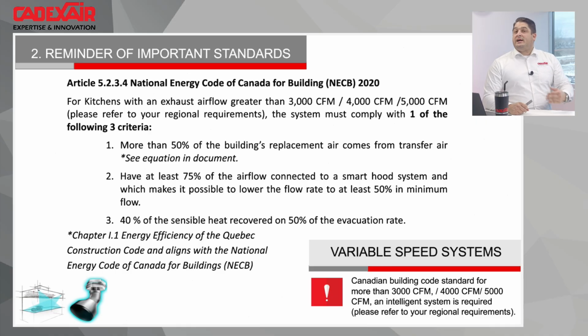An example of that, we have done in a hospital in the past. They have a lot of surgical rooms, so they bring in a lot of air to keep them in positive pressure, to be sure that no contaminant enters the room when people have an operation. So in that case, if you have a lot of fresh air that you need to put out of the building, and it's more than 50% of the hood, you don't have to put in a demand control system.